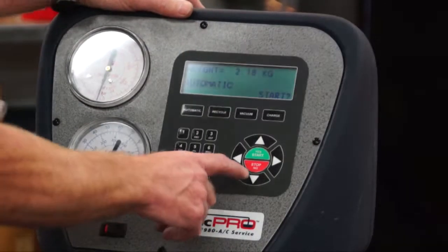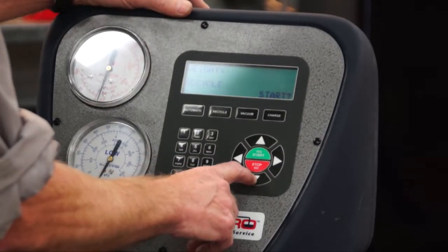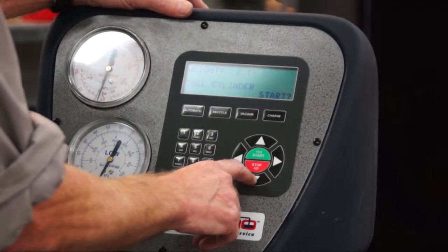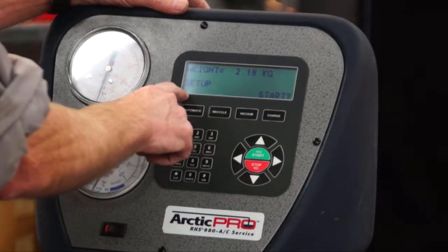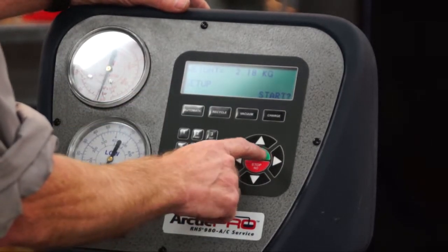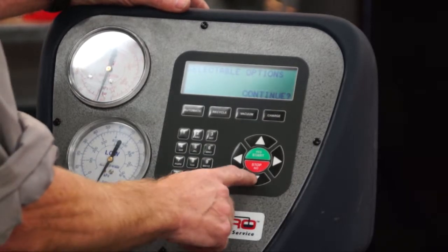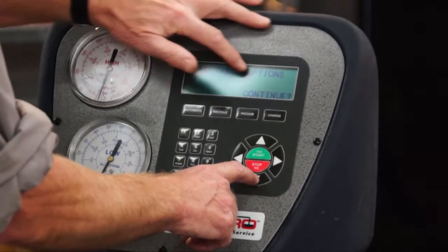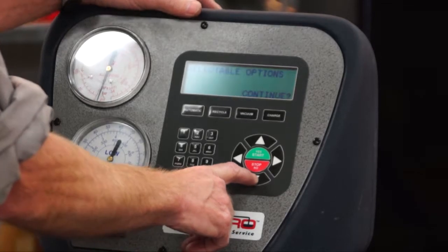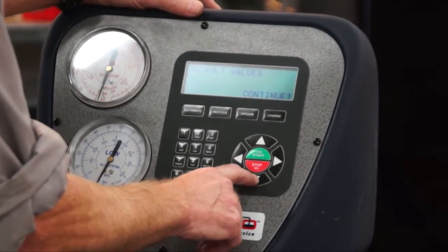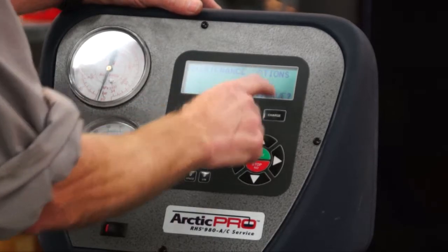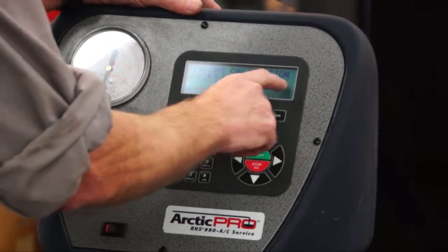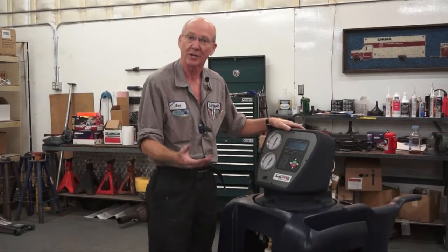I'm going to hit the down arrow until I get to setup. Then I'm going to hit yes, setup, start. Then I'm going to hit the down arrow again because I'm in selectable options. That's how I'm going to get the maintenance options. Maintenance options, I'm going to hit yes. Perform calibration check, yes or no. We can perform a calibration check.